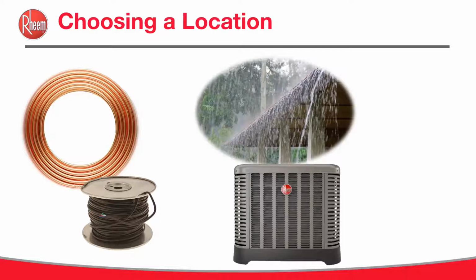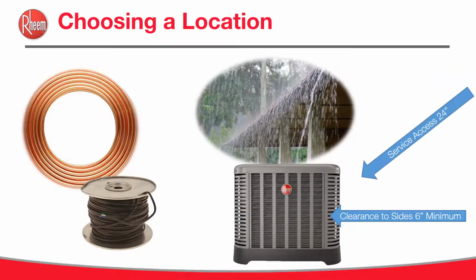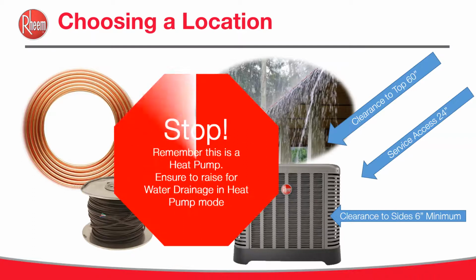This is especially important with a heat pump because large amounts of water or snow entering the unit can impact blade and motor life. If water cannot drain away in freezing conditions, this will affect the unit operation as well. Clearances: 6 inches minimum. We do recommend 12 inches to the sides of the grills. You want 24 inches service access and a minimum of 60 inches to the top of the unit. Remember, this is a heat pump, so it must be raised off the ground for proper drainage.